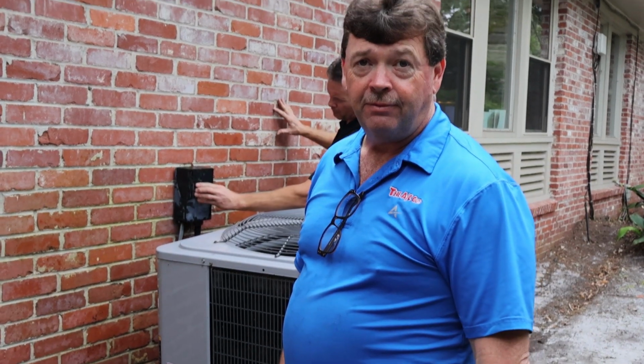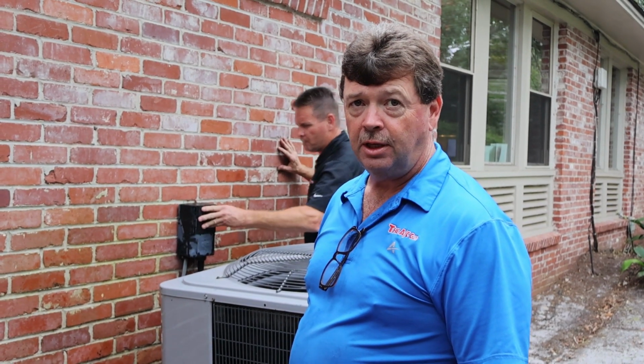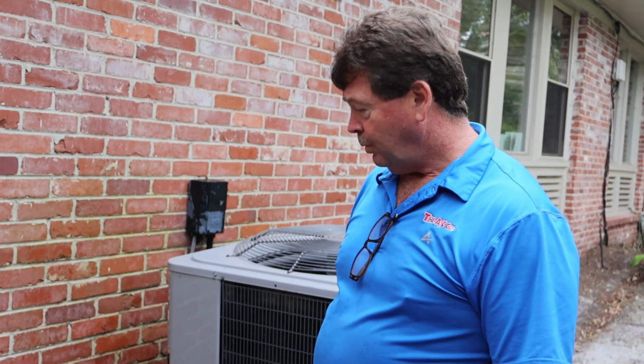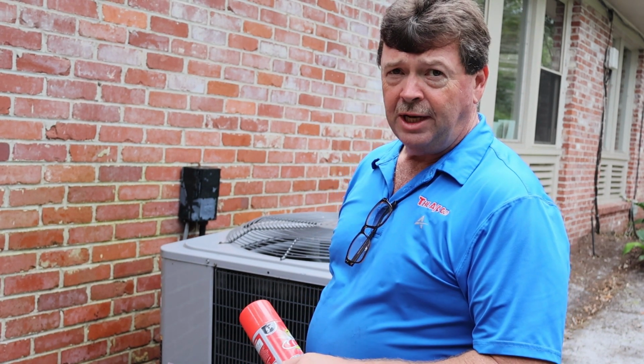We have concluded the outdoor portion of our preventive maintenance. To reiterate, we've checked the freon levels, subcooling, superheat, all within parameters. Checked the capacitor, it was a little weak. We're going to replace it. Contactor has some wear, moderate, maybe change it next PM. The condenser fan motor's in good shape.